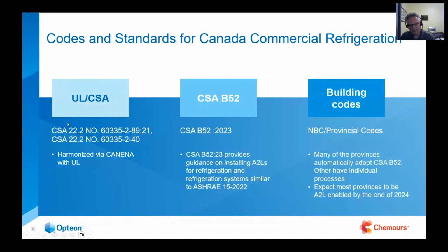But oddly enough, both of these standards do have some areas that cover not only design, but installation. So the manufacturers of equipment need to follow both of these when they're designing their equipment and providing guidance on installation. And certainly when we look at air conditioning units, when you see that first box shipped to your location, you go to install it, there's going to be a document in there that's going to have a few more pages in it than before, which is going to provide guidance on the installation requirements.